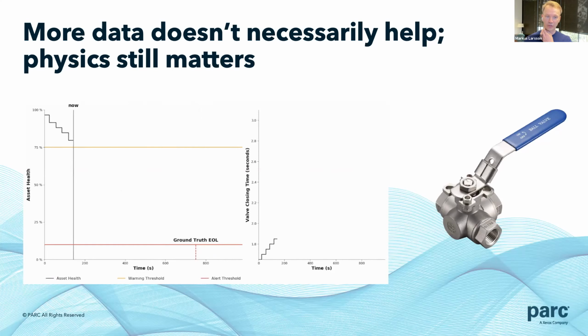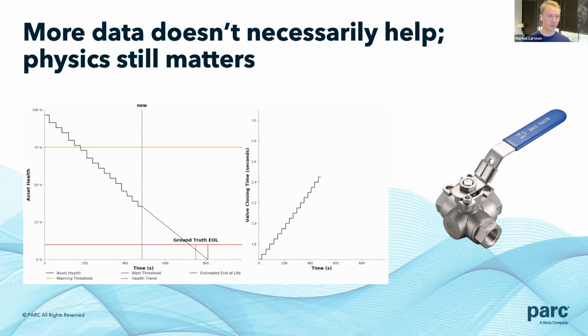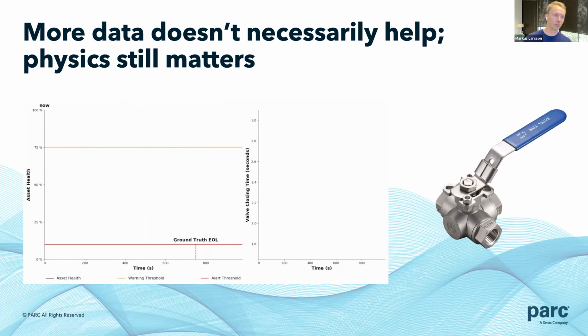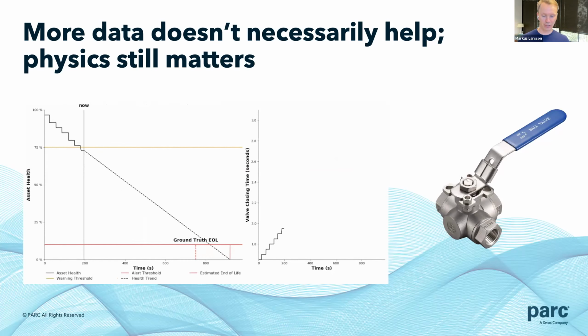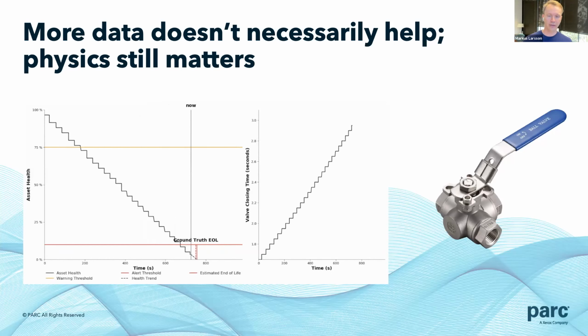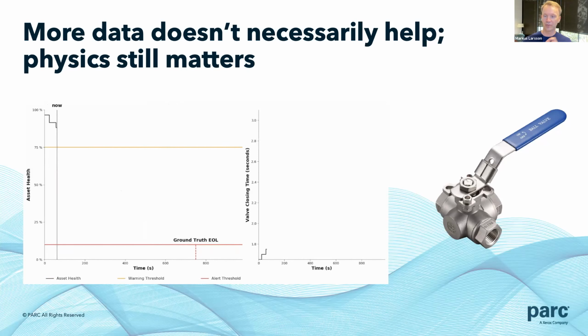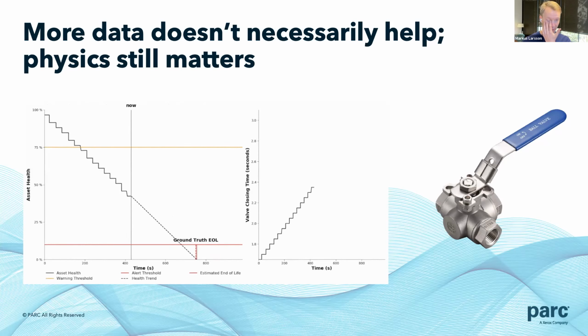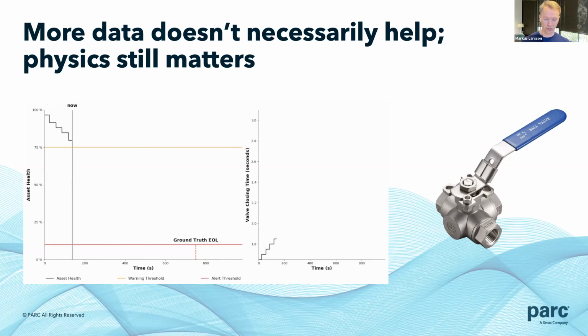As an illustration, what you're seeing here is an algorithm monitoring the health of a ball valve, shown in the picture on the right. The valve controls the flow of viscous liquid. In normal operation, the liquid builds up and accumulates within the valve, leading to more sluggish flow, to the point where the valve can no longer operate and hits its end of life, stopping production. We've predicted asset health based on the closing time of the valve - as the closing time increases due to liquid accumulation, the asset health declines almost linearly, up until it reaches end of life and is no longer operational.